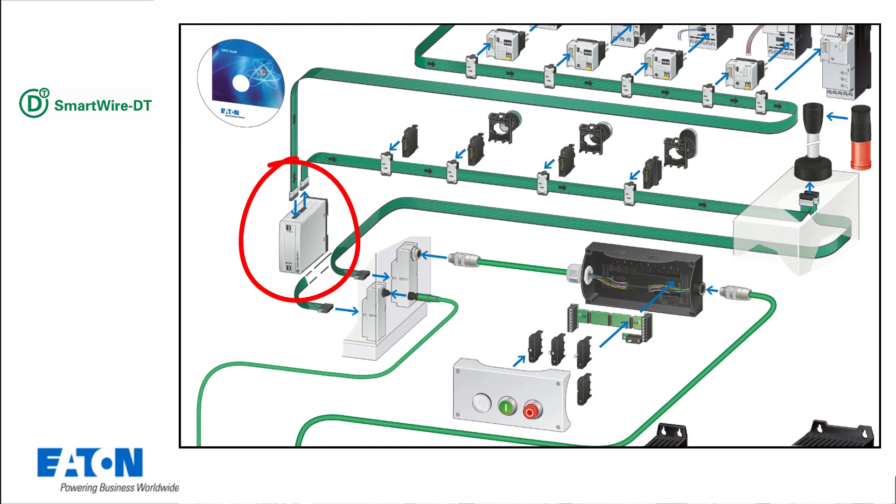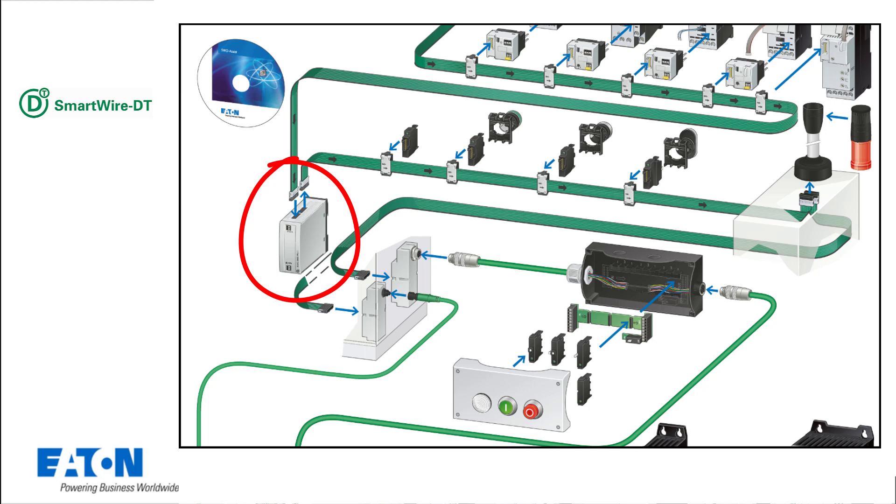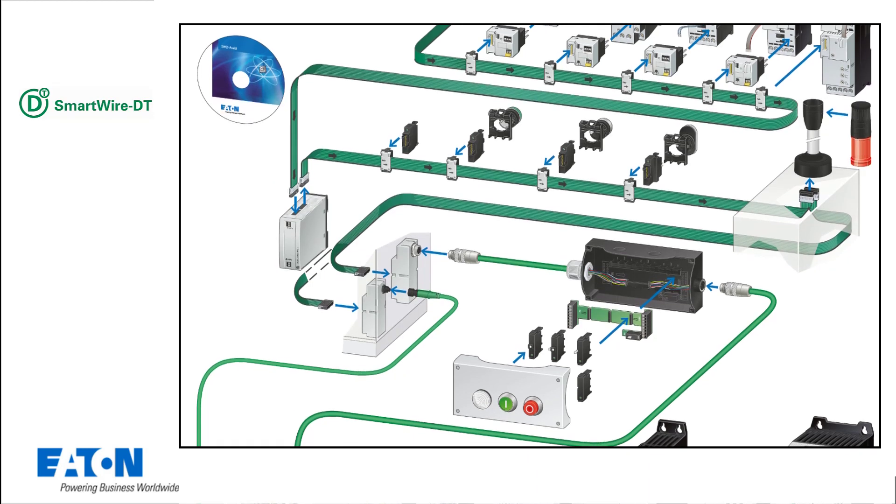Power feed modules can be used to provide an additional 15V DC power supply for the devices and 24V DC control voltage supply for contactors, if required. The need for a power feed module is automatically indicated in the SmartWire DT assist software or in EasySoft.